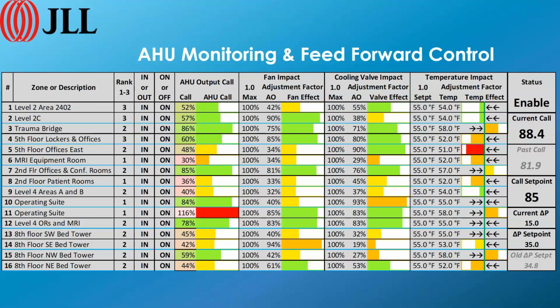And so this one looks at an air handler output call. That is the 5th column in. And the output call is what's happening from the fan power boxes or the VAV boxes coming back. What are those boxes saying to the air handling unit? So in one case, that first line, we've got 52%, sort of moderate. As you move down, you'll see there's one that's at 86%. That's calling for a little bit more.